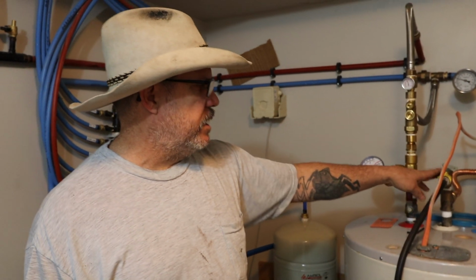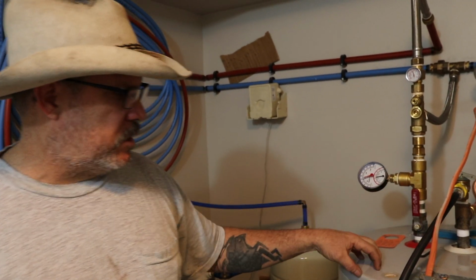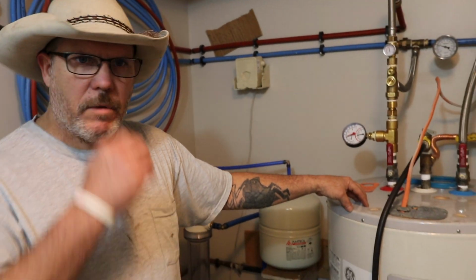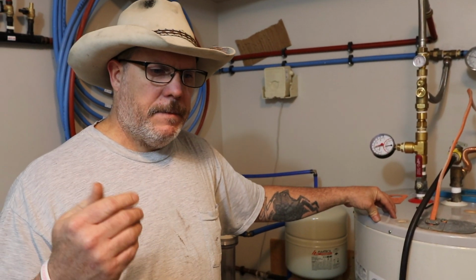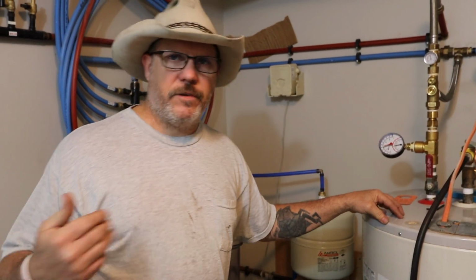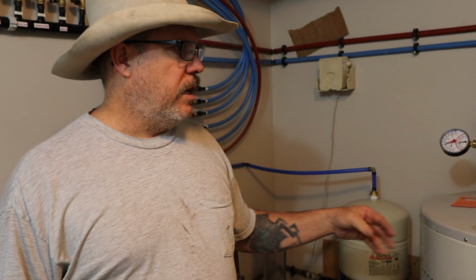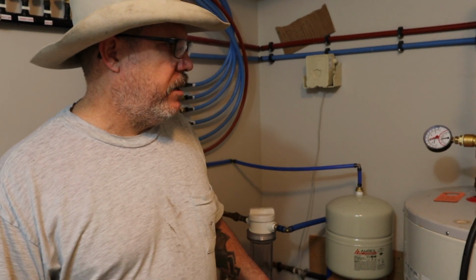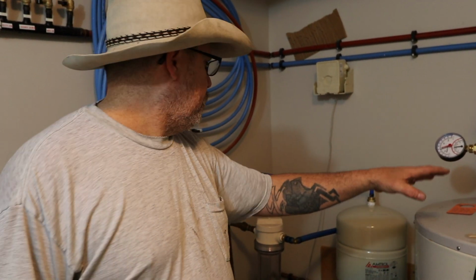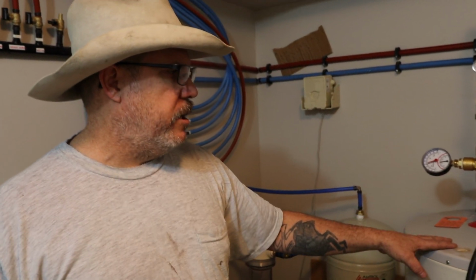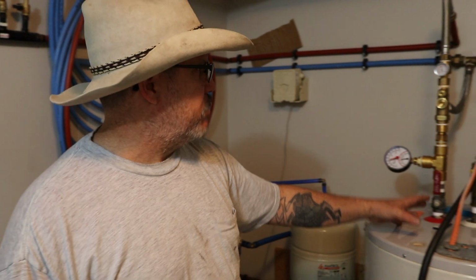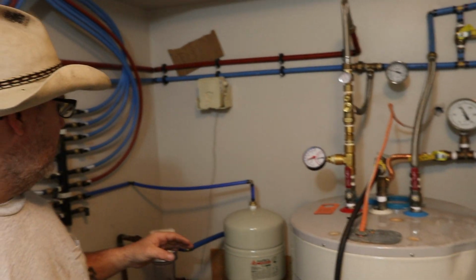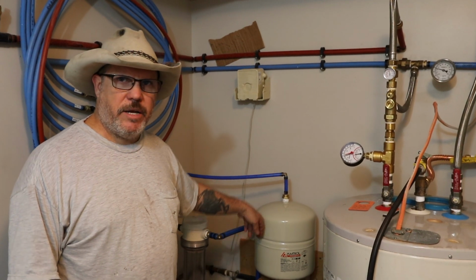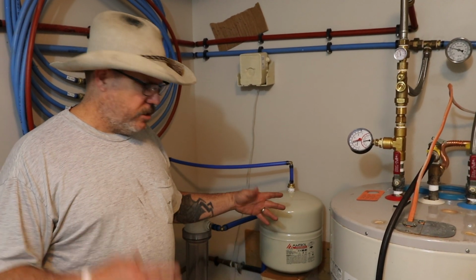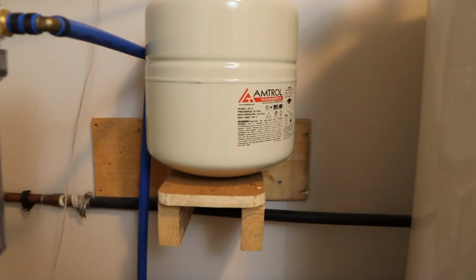I haven't had a problem with it, but basically, if this valve fails, this thing can build up so much pressure, because city water, most municipalities, has a check valve or a backflow preventer of some sort. Once it leaves the city main and comes your way, it doesn't get back. So like the old systems, it equalized the pressure that way, but nowadays you've got a backflow preventer, so all of your water, once you're heating it up, expands. It'll expand your hot water side, and it'll expand your cold water side. So I highly recommend putting an expansion tank in, depending on the size of your system. Put an expansion tank in here.